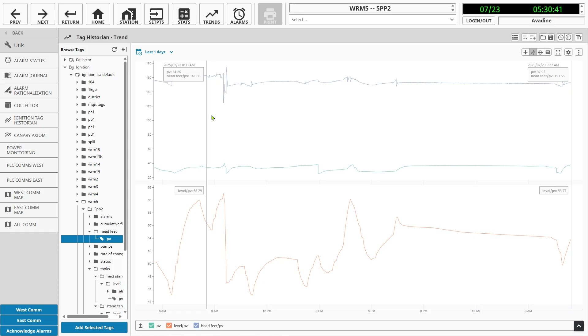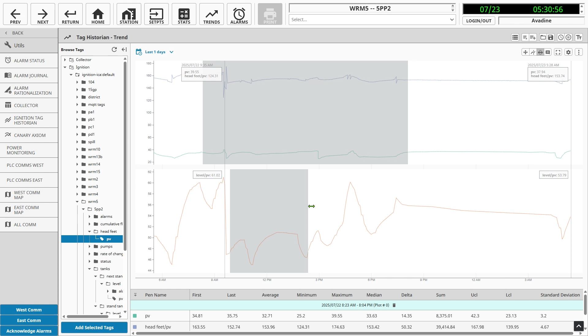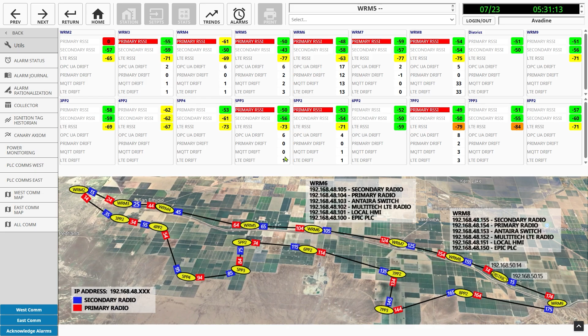One of the things we were wanting to really expose was the RSSI of our radio system, because communication was such a big deal. The Cambium radios didn't have an API that we could pull on, but it had SNMP. So leveraging node red in the Epic PLC, we got the MIB file. We were able to extract uptime, RSSI, what channel's being used, what the power output is, and we pulled in those critical data points from the primary and the secondary radio.